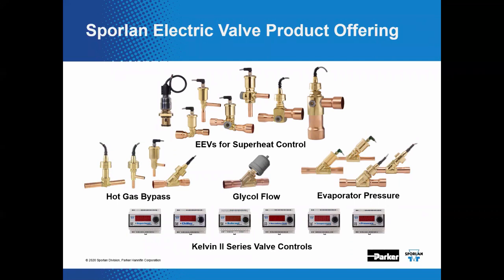Now, these electrically actuated, electronically controlled valves can be used to not only control superheat, but things like hot gas bypass, glycol flow. You know what? You're going to have to send me back to school so I can say glycol flow. Wow. In a secondary application, evaporator pressure regulation as well. There are also specific standalone Kelvin 2 series controllers available to help complete the package.